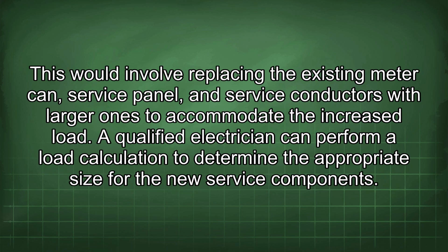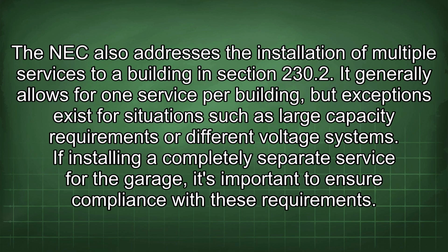This would involve replacing the existing meter can, service panel, and service conductors with larger ones to accommodate the increased load. A qualified electrician can perform a load calculation to determine the appropriate size for the new service components. The NEC also addresses the installation of multiple services to a building in section 230.2. It generally allows for one service per building, but exceptions exist for situations such as large capacity requirements or different voltage systems. If installing a completely separate service for the garage, it's important to ensure compliance with these requirements.